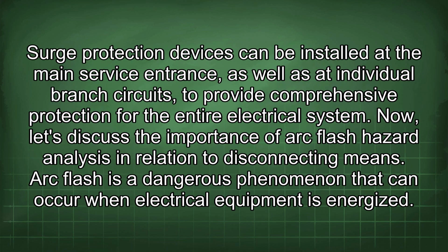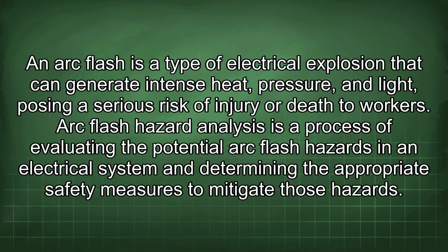Surge protection devices can be installed at the main service entrance, as well as at individual branch circuits to provide comprehensive protection for the entire electrical system. Now let's discuss the importance of arc flash hazard analysis in relation to disconnecting means. Arc flash is a dangerous phenomenon that can occur when electrical equipment is energized. An arc flash is a type of electrical explosion that can generate intense heat, pressure, and light, posing a serious risk of injury or death to workers.